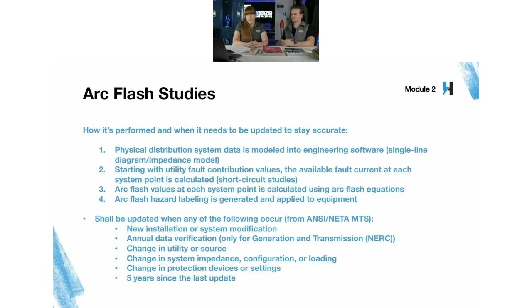All right, why is it helpful? How do you use the information? Well, this one hopefully is a little bit more understood by people, but still, it's going to give you what the available incident energy is at a location if an arc flash were to occur. So it'll give you that incident energy, the arc flash boundary, again, how far out the hazard is so that people know how to set up their barriers and barricades appropriately, or station an attendant outside of that boundary to keep people away. It'll help identify what PPE is required, the minimum ratings of those PPE articles that you're going to wear and rely on, as well as just making sure that your voltage levels is also going to be included on these arc flash labels.